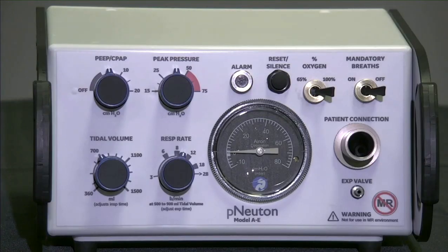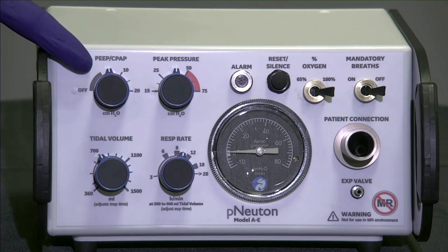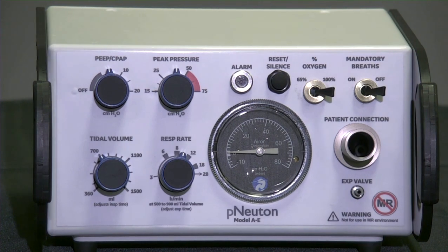Moving to the front panel, we will start with the 4 primary controls for ventilator setup. PEEP CPAP control. The PEEP CPAP adjustment adjusts to 20 centimeters of water pressure with automatic sensitivity for changing patient needs. The demand flow rate is provided up to 140 liters per minute for the spontaneously breathing patient. The FiO2 delivered during spontaneous breathing is set by the percent oxygen control.